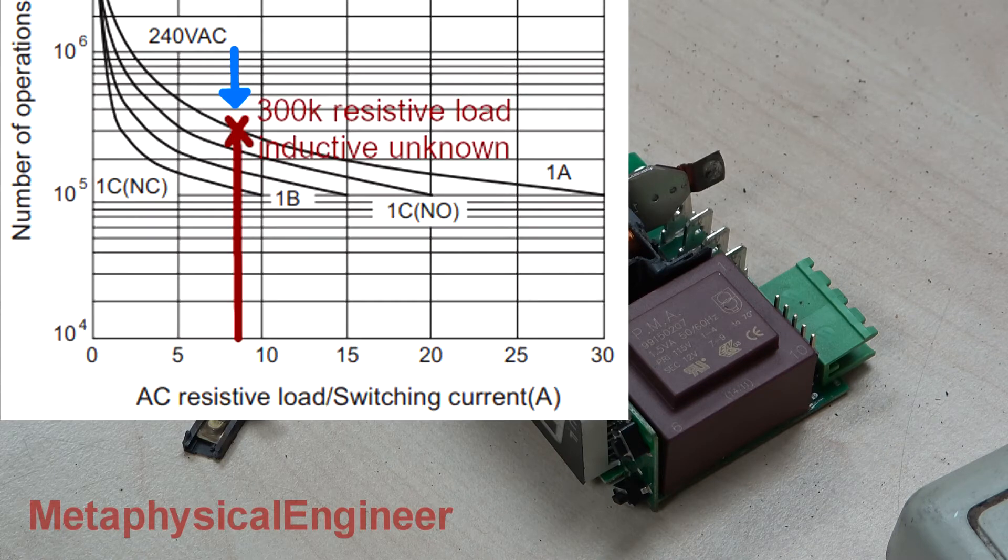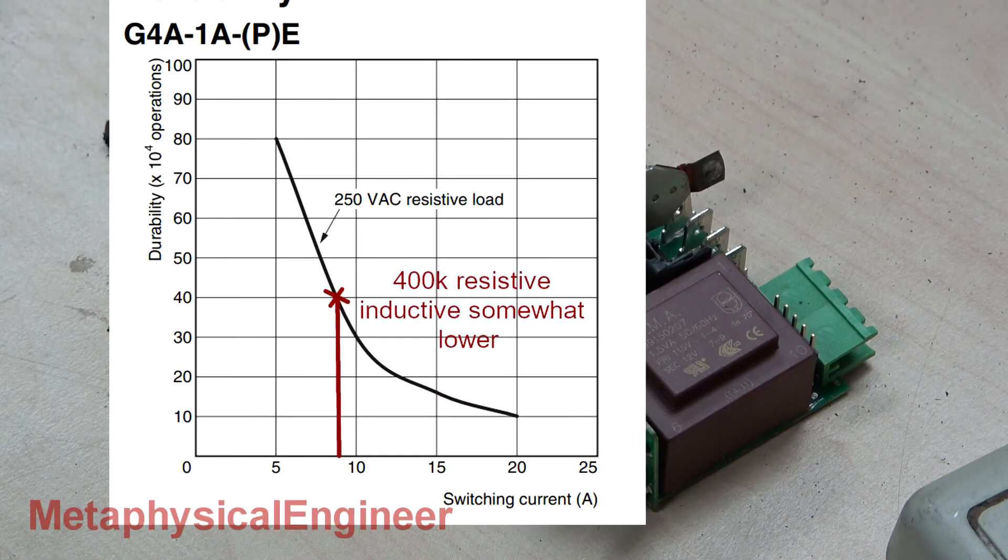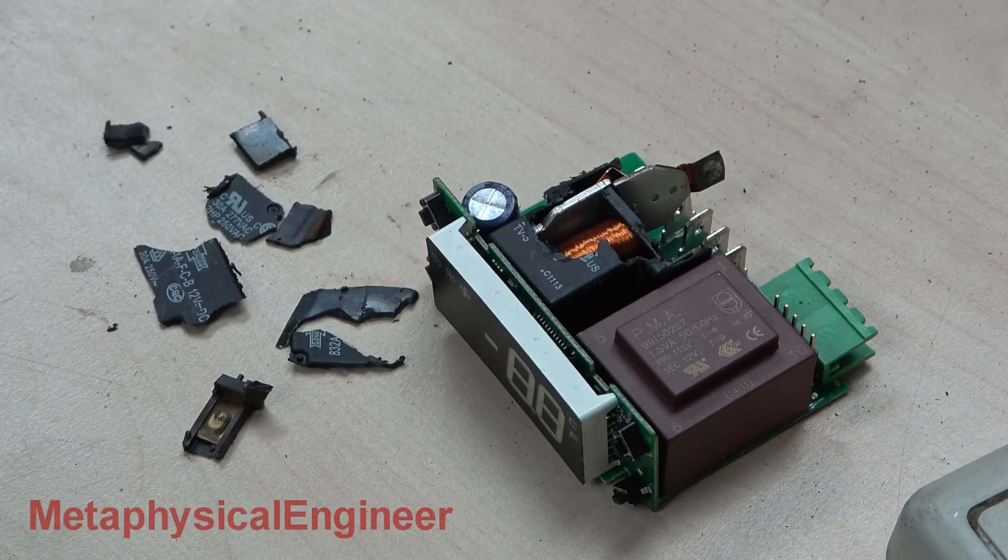In fact, it may have greatly exceeded its rated service life for those conditions. The Omron relay would still be purring along, waiting for some other major component to give up first. Hope you enjoyed this little dive into the frustration of dealing with small commercial refrigeration controllers.